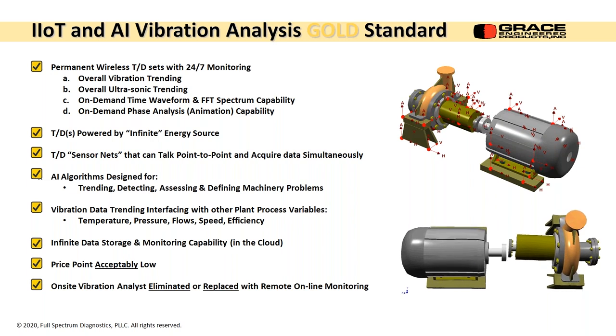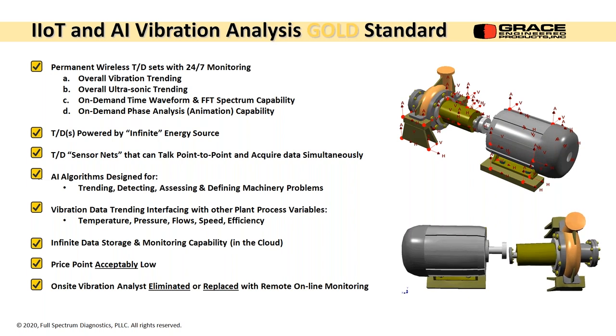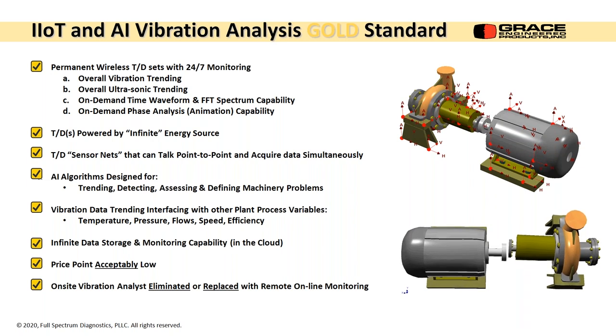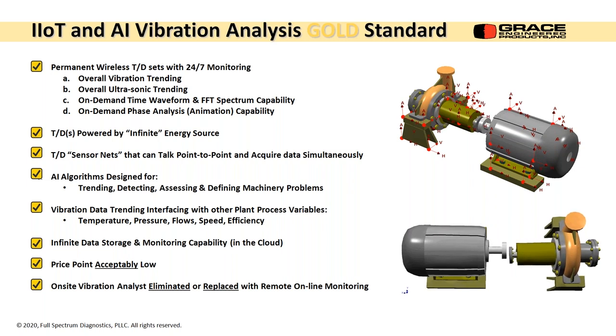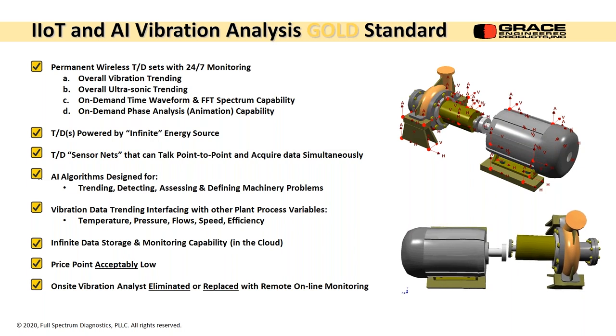You'll get really small impacts that you can only see in the high frequency range. A lot of people are going to that, hoping for transducers that can do both. On-demand time waveform and spectrum capability. It's real important if you have an overall level that exceeds a certain criteria that you do a waveform or a spectrum to see what's really going on. And there's some clue frequency content wise what's happening. And then probably the hardest one is on-demand phase analysis, or, you know, in my case, animation capability.